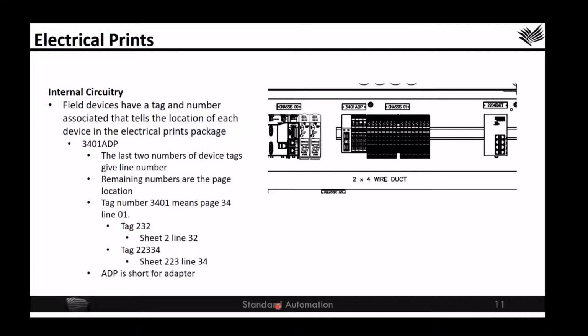The last two numbers of the device tag number give the line number that the device is found on inside of the electrical prints package. The remaining numbers are the page location. So for a tag 3401, it means that it's on page 34, line 1. Tag 232 would be on line 32, sheet 2, and tag 22334 would be on line 34 of sheet 223. The ADP just means that it's an adapter.